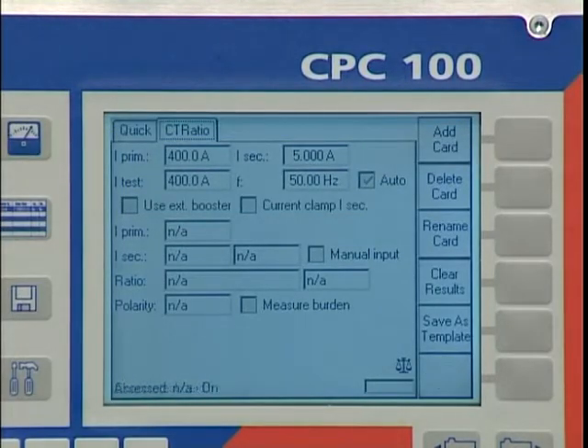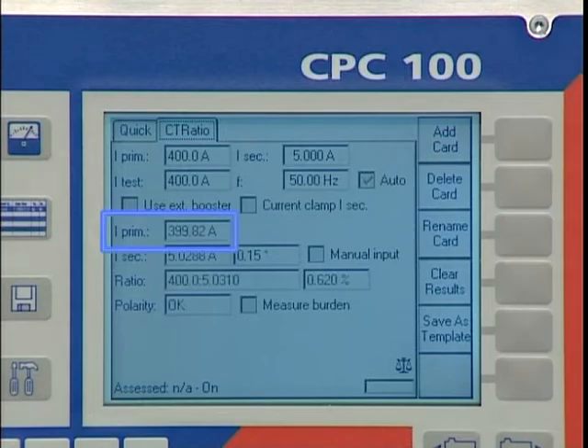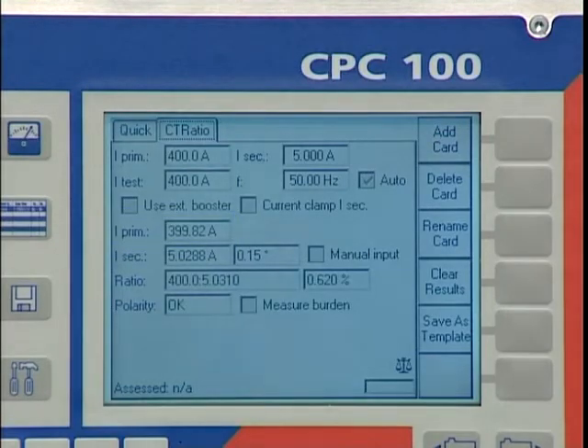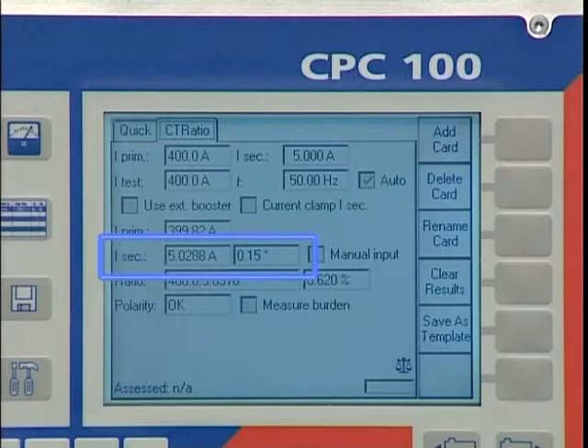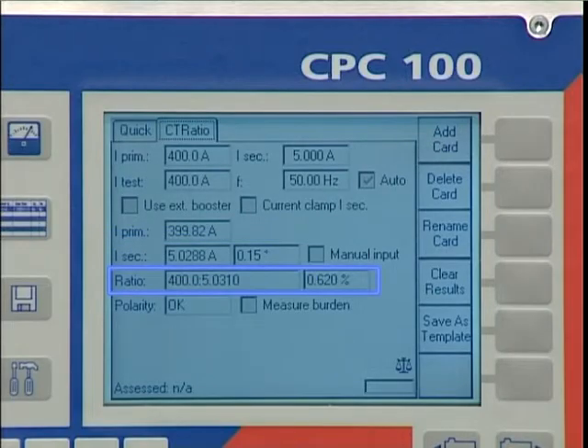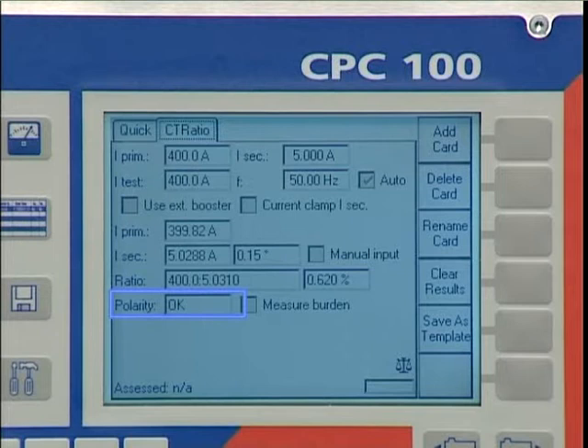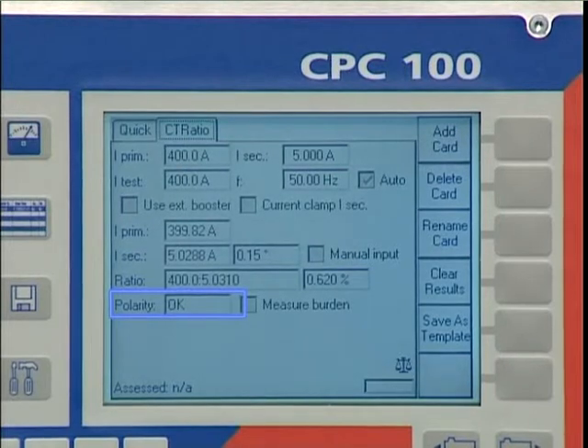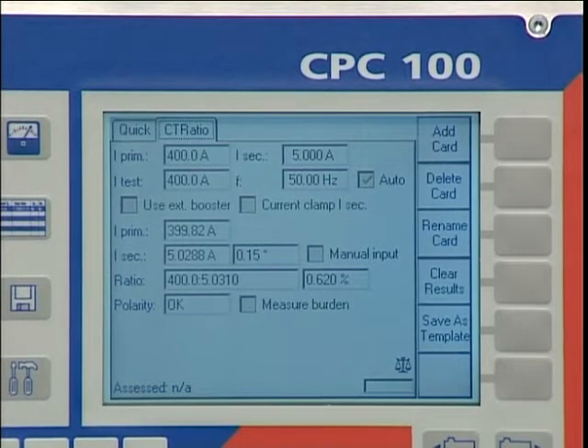From the resulting test measurement, we get the test current which was injected on the primary side, the magnitude and angle of the secondary current, the ratio with error in percent, and the assessment of the polarity of the CT.